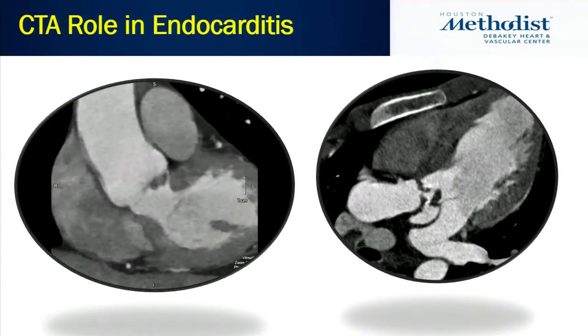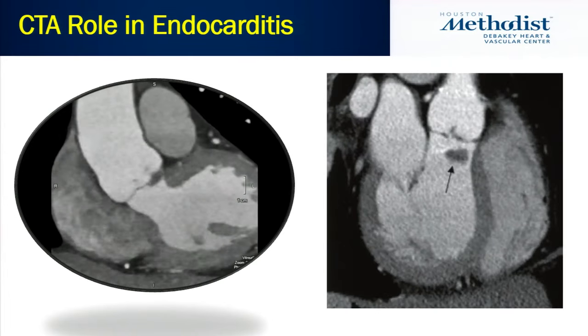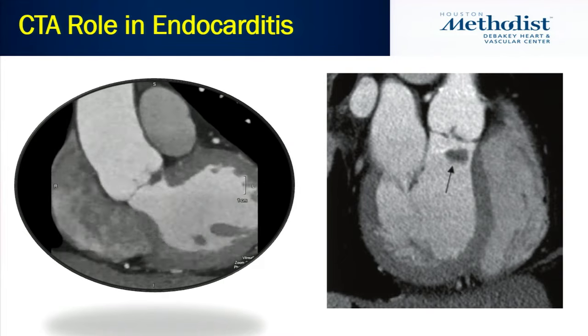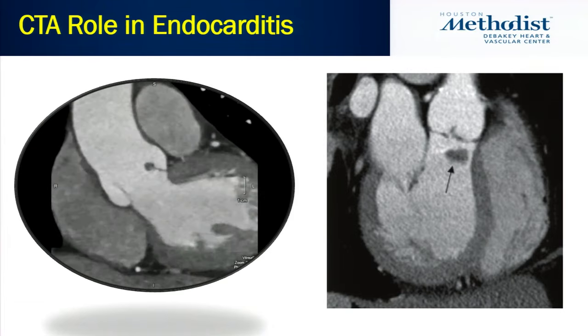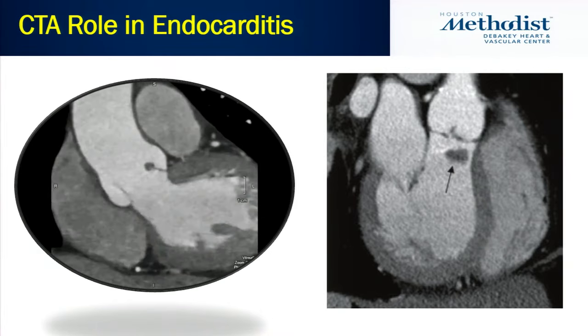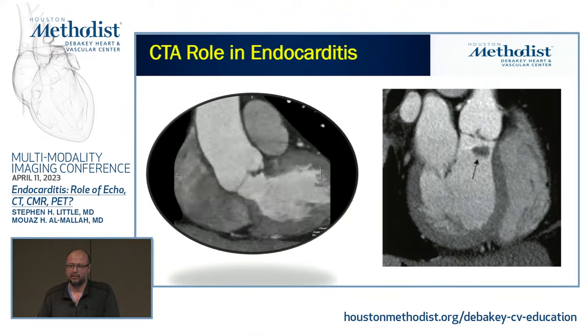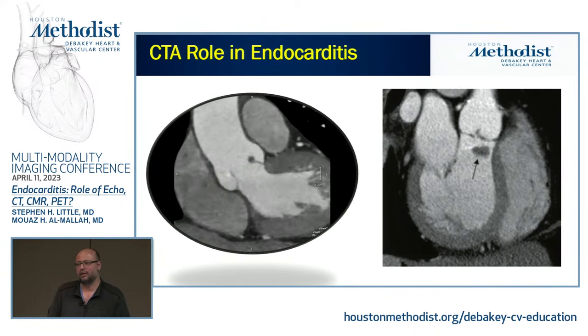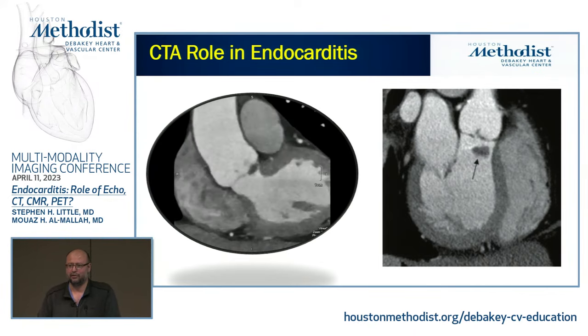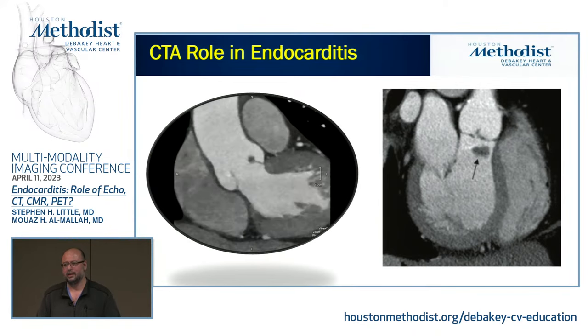We use retrospective gating for these valve cases. Our temporal resolution on our scanner is about 60 to 65 milliseconds, so a highly mobile lesion we might detect. However, if you're scanning on a system with worse temporal resolution — some systems in clinical use have about 200 to 300 milliseconds — you may not be able to see a small, highly mobile vegetation because it's moving too fast during acquisition.